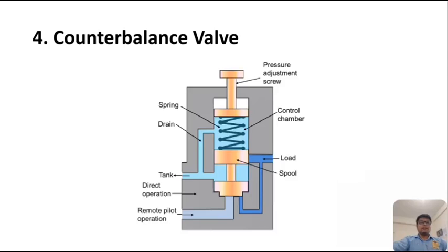Therefore, a lower spring force is sufficient, and it leads to the valve operating at a lower pilot pressure, and hence the power consumption will reduce, the pump life will increase, and the fluid temperature will decrease.